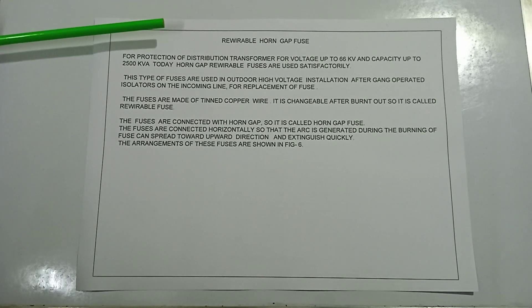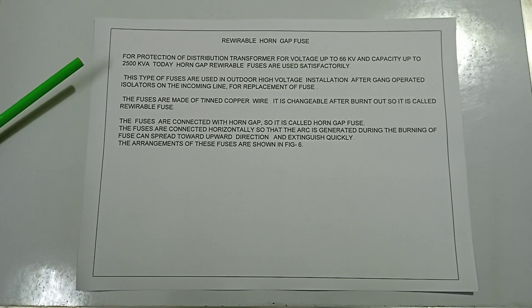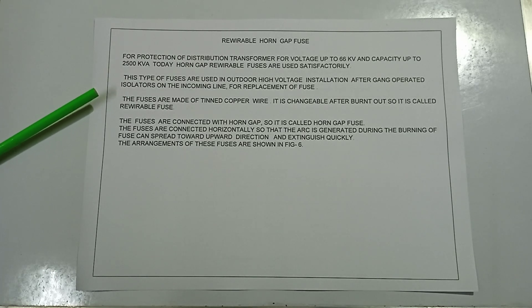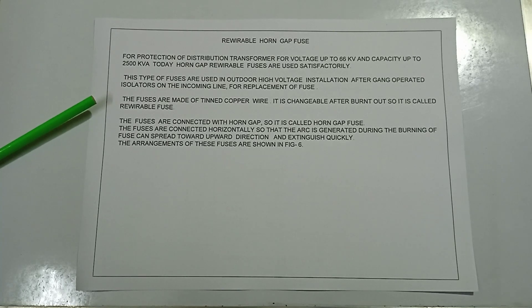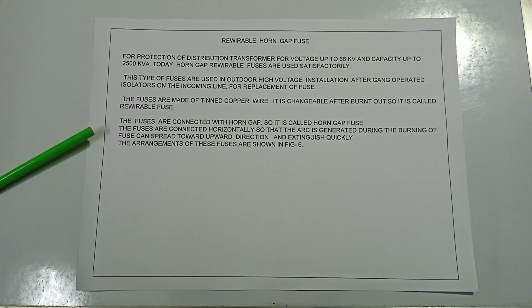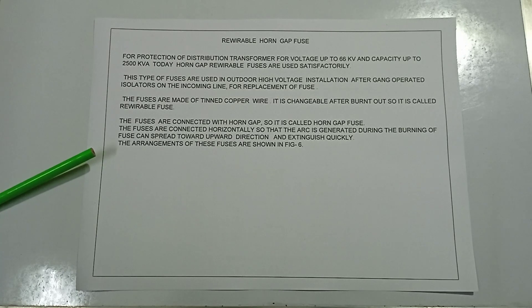Rewireable horn gap fuses are used for the protection of distribution transformers for voltages up to 66 kV and capacity up to 2500 kVA. These fuses are used in outdoor high-voltage installations after gang-operated isolators on the incoming line. The fuse element is made of tin wire, which is replaceable after burning out — hence it is called a rewireable fuse. The fuses are connected horizontally with a horn gap so that the arc generated during fuse burning spreads upward and is extinguished quickly.